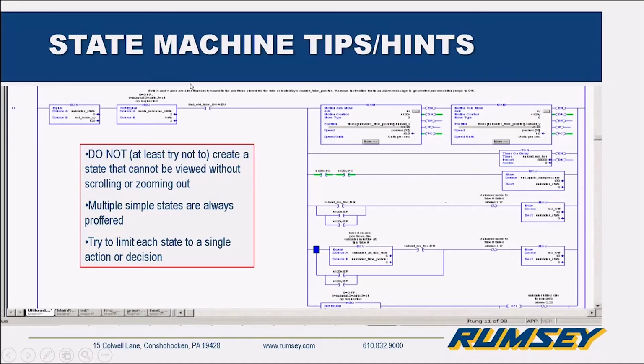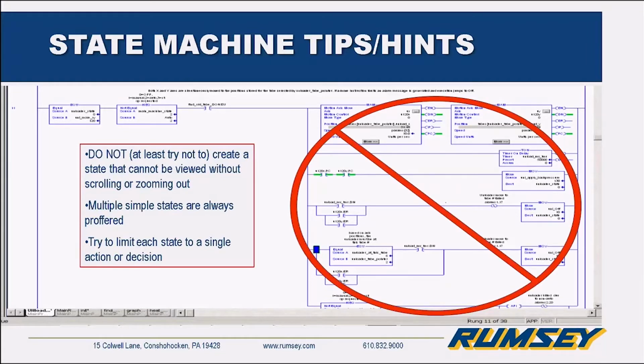When using a state machine, try not to have your state machine require you to scroll in or zoom out to see all the code. Multiple simple states are preferred. In other words, do the move, wait for the reaction, move on to the next one, if at all possible. It's just easier for troubleshooting purposes. I'm not saying it wouldn't work, but it's easier for troubleshooting. You can see the entire rung of code rather than having to zoom in and out, perhaps not being able to read because you have to zoom out so far. You basically have a small little program within one particular line in your code.